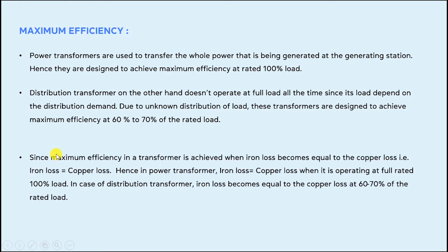Maximum efficiency in a transformer is achieved when iron losses become equal to copper losses. In power transformers, iron losses equal copper losses when operating at full rated 100% load. In distribution transformers, iron losses become equal to copper losses at 60 to 70% of the rated load, since they are designed to achieve maximum efficiency at that point.